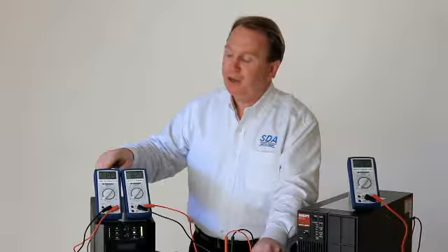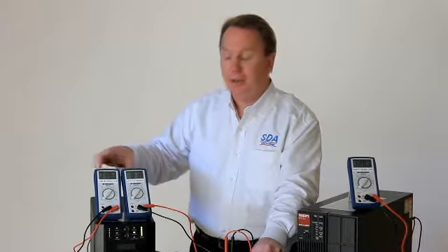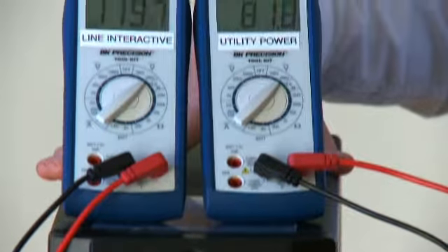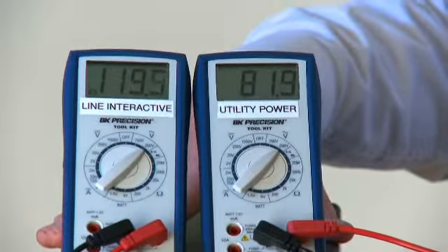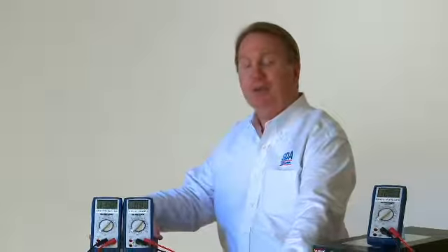Your batteries have taken over, your power is restored, but this unit right now is leading to one of the largest expenses in single-phase UPS, the battery purchase. People buy pallets of batteries in protecting the UPS from this event right here. You don't hear it, you don't see it because it's stuffed in a closet. But the fact is, battery replacement represents the highest cost of operating drawback of the line interactive UPS today.